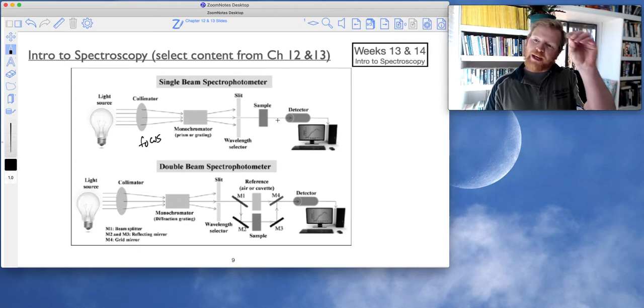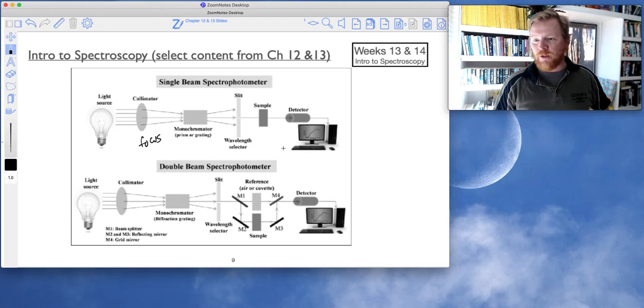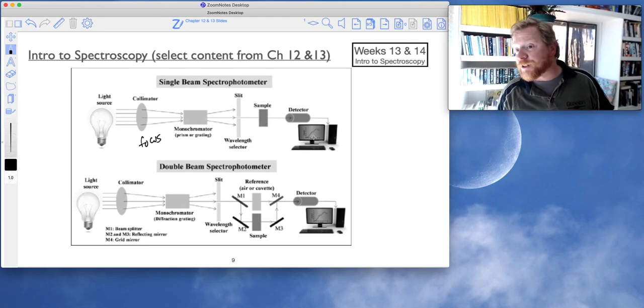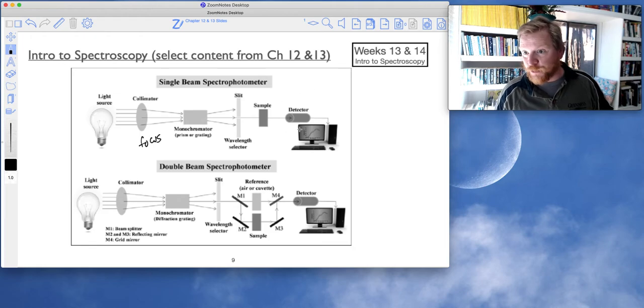Then you would replace your background cuvette with your sample cuvette, stand on one foot, hold your breath, cross your fingers, do all the stuff. And then your computer system, your detector, will work out that ratio of ratios to give you the true absorbance or transmittance spectra.